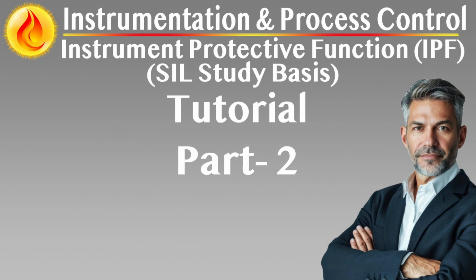Influence on SIL assignment. Personnel safety consequences drive the assignment of higher SIL targets, often requiring SIL-2 for single fatality credible risks, SIL-3 for multiple fatality or high exposure scenarios, and SIL-1 only when mitigated consequences are minor and fully documented. The higher the consequence, the lower the allowable PFD and the greater the scrutiny on design, verification, and testing of the IPF.